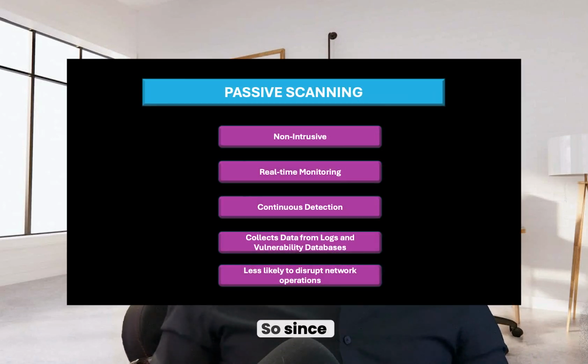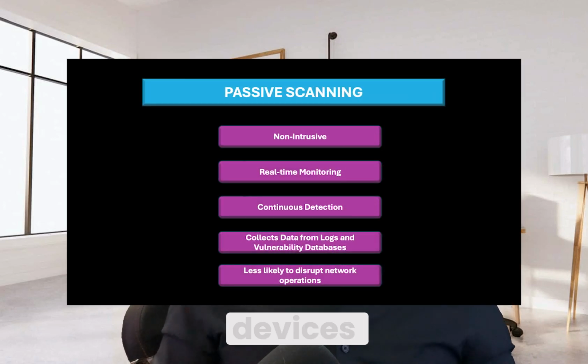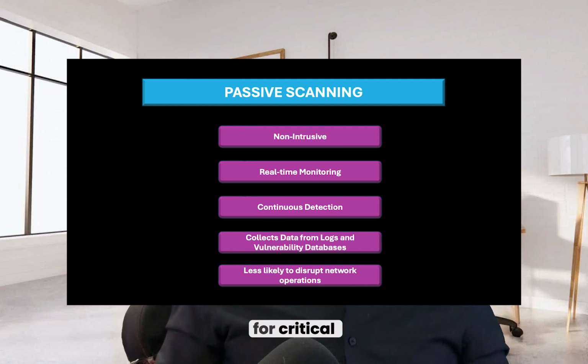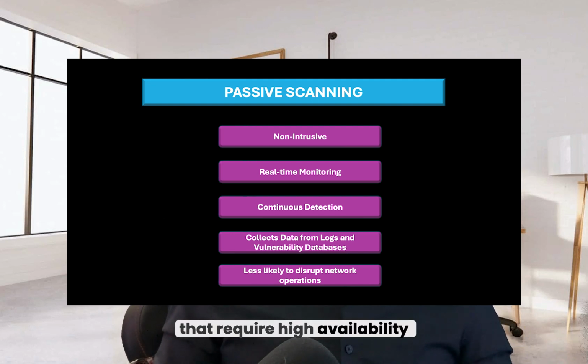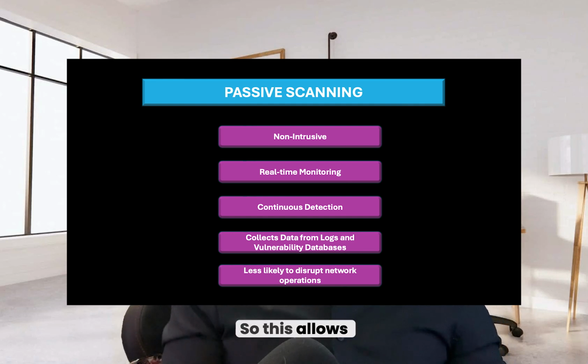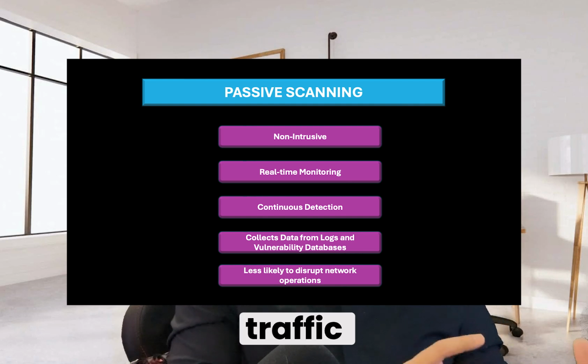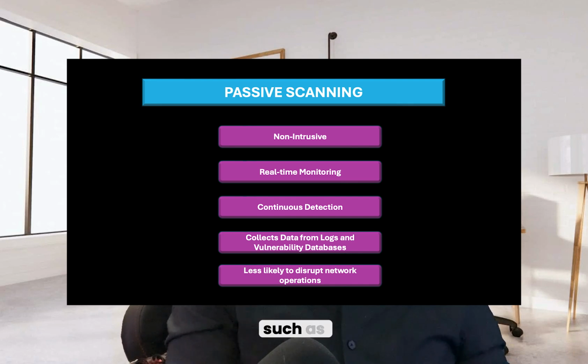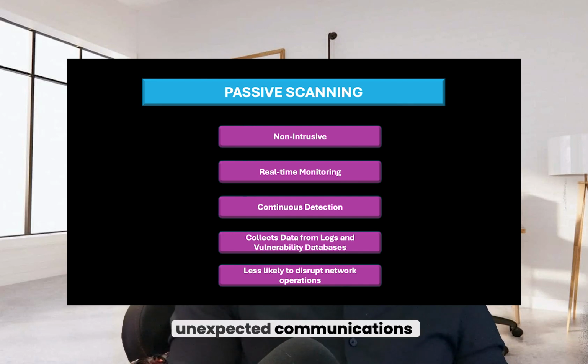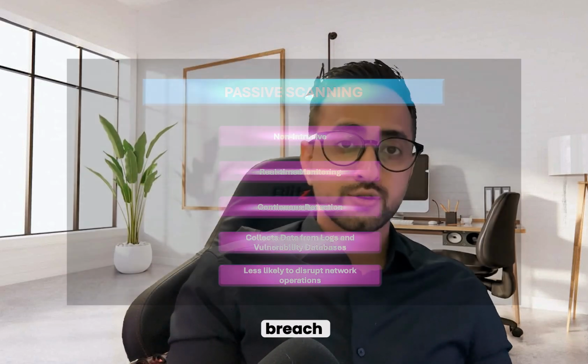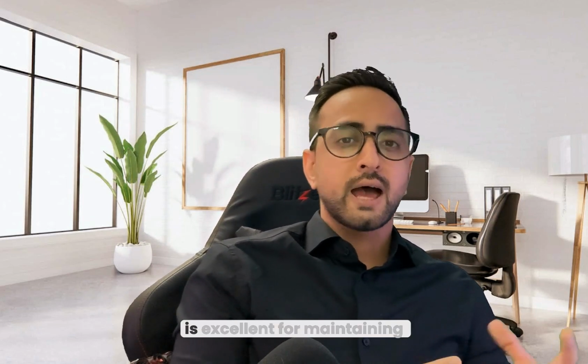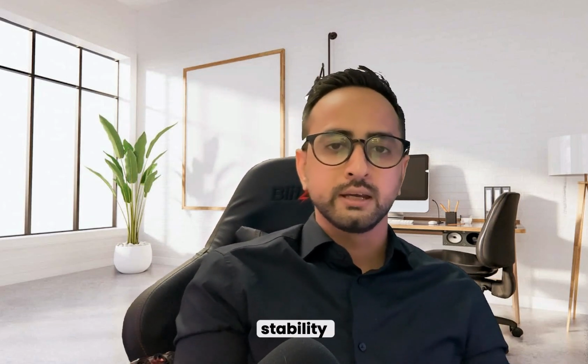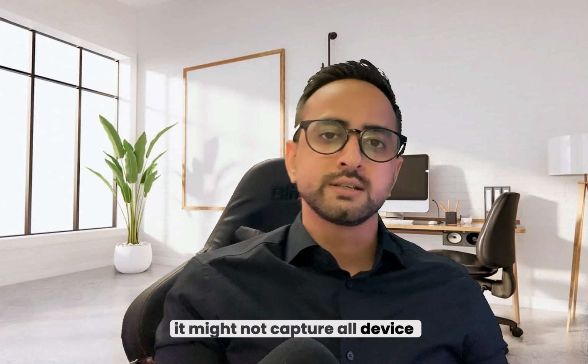Let's look at some technical facts. Since passive scanning doesn't interact with devices, it's ideal for critical systems that require high availability. Passive scanning provides continuous, real-time visibility into the network. This allows OT engineers to monitor traffic patterns and detect anomalies such as unexpected communications that could indicate a security breach. While passive scanning is excellent for maintaining stability, it might not capture all device details.